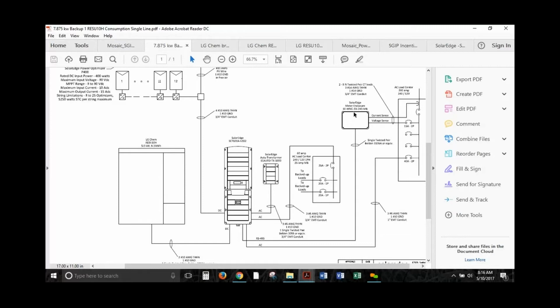This is the meter with enclosure, and this is the brains behind the system, or one of the brains, and this is where those CT clamps get installed. Essentially, this is the area that gets programmed, part of the area that gets programmed to tell the inverter to either charge the battery, discharge the battery, or go to the backup loads.